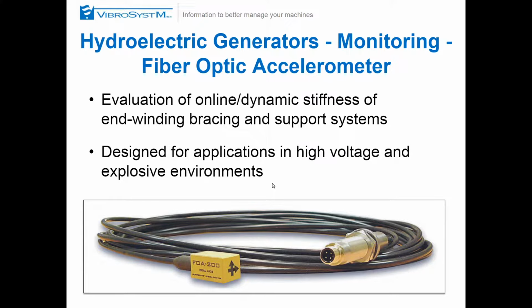Now, I mentioned that end winding vibration is more commonly used on turbo generators, but it is also used on hydro generators, and in fact, it's also used on large motors, on big SAG mills and ball mills, because they also have end windings. They also have epoxy mica insulation, which does not like to vibrate.